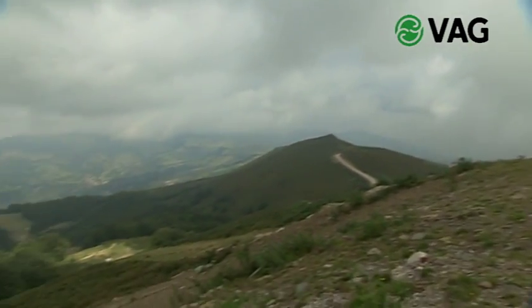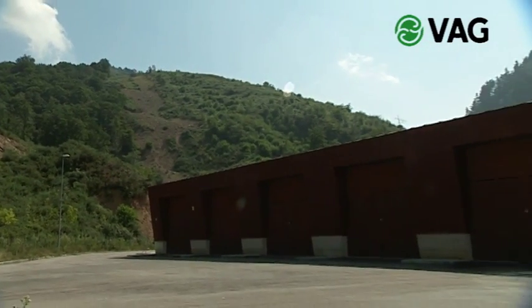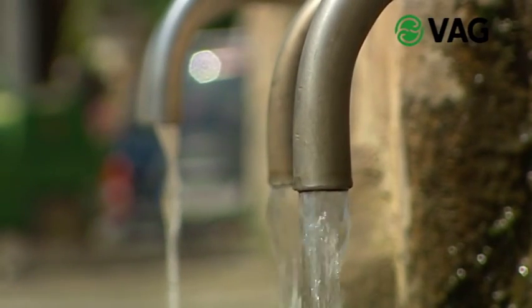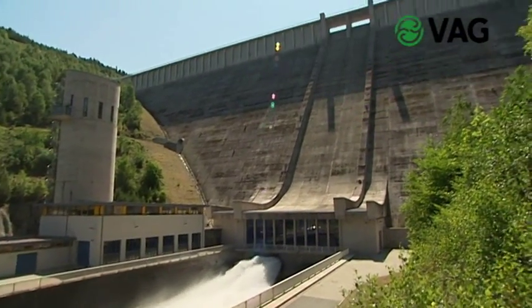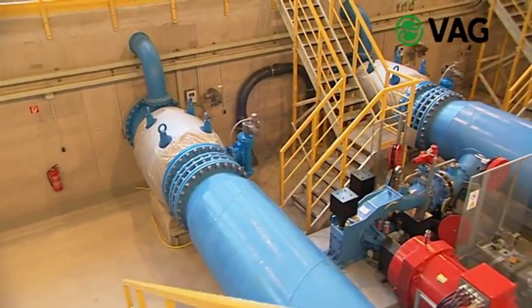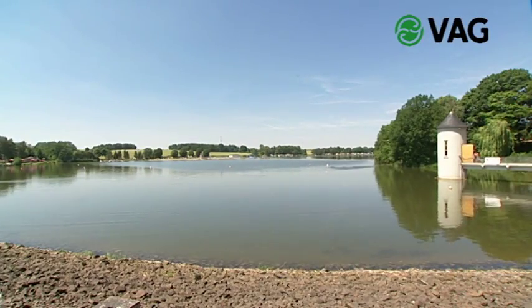Here in a water supply pipeline in the north of Spain, VAG plunger valves with a nominal pressure of PN100 have been installed because of the large differences in altitude and the resulting high pressures. VAG plunger valves are suitable for many different applications: as bottom outlet valves in a dam, as flow control valves or pipe burst safety devices, as pressure and level control valves, and also as purging or draining valves. Properly designed, VAG plunger valves operate cavitation-free for decades.